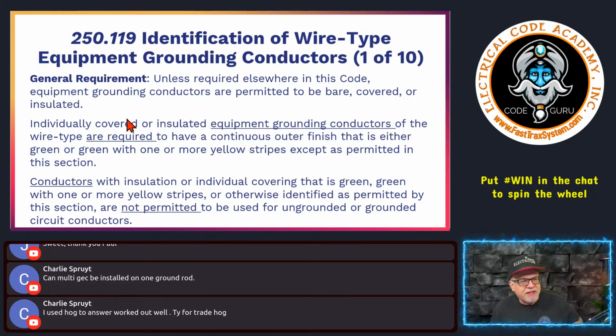All right, so let's look at 250.119. We can look at 250.118 and see all the different types of equipment grounding conductors, but we're going to talk about the wire type today. So we've learned earlier that unless required elsewhere in the code, equipment grounding conductors are permitted to be bare, covered, or insulated. So that's the general rule. Although you saw a couple days ago when I talked about healthcare facilities that have a patient care area or space, depending on which code cycle you're in, they're going to require that it be an insulated equipment grounding conductor. So that's an example when you see something in code that says unless required elsewhere. That's what they mean. Another example would be a swimming pool application where they require an insulated equipment ground. That would be an example of elsewhere in the NEC.